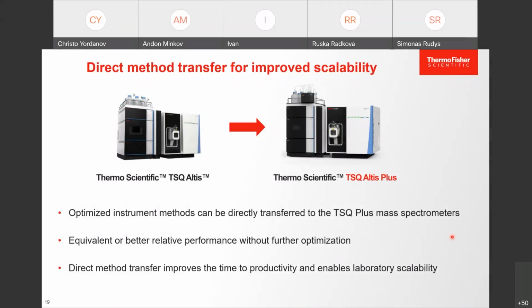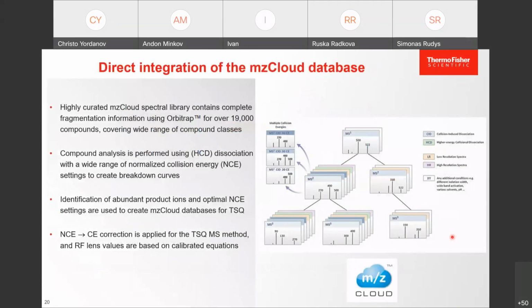Of course, it's not a big deal in general, but the next step I want to mention is how we can improve this method creation by using our mzCloud library. Some of you probably know, if you are using Orbitrap instruments, that most of the time you probably use our mzCloud online or mzVault offline library, which consists of high-resolution accurate mass spectra, and includes around 19,000 compounds, covering a very wide range of compound classes. And this library is built by injecting real standards on the Orbitrap mass spectrometer.